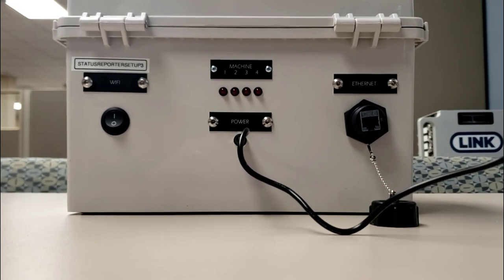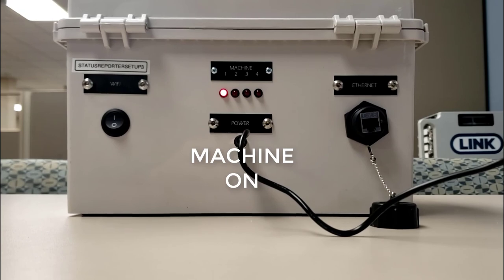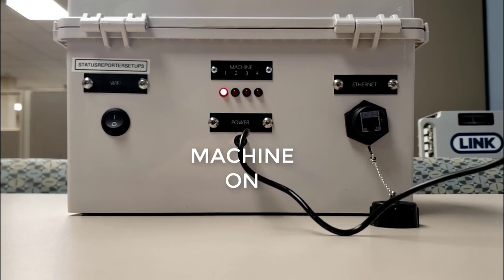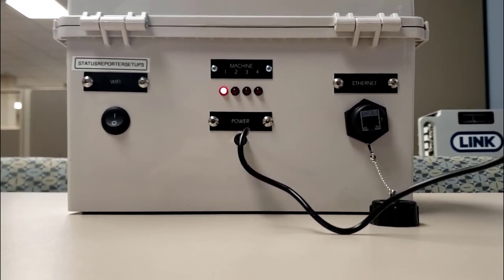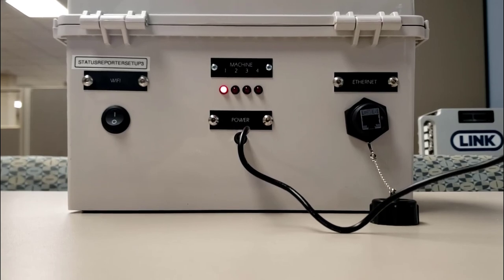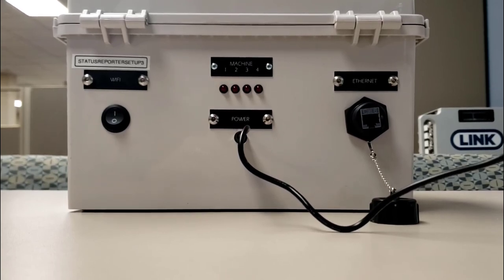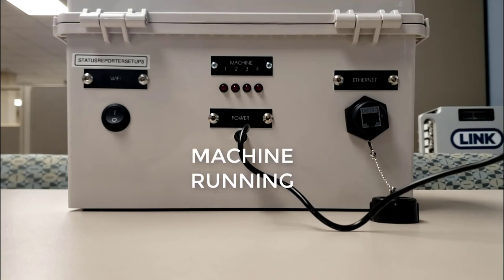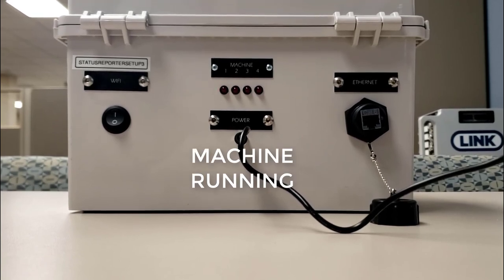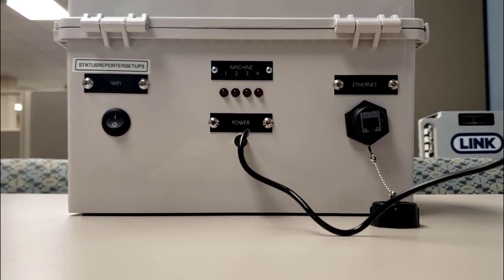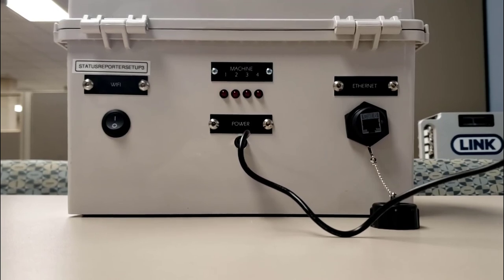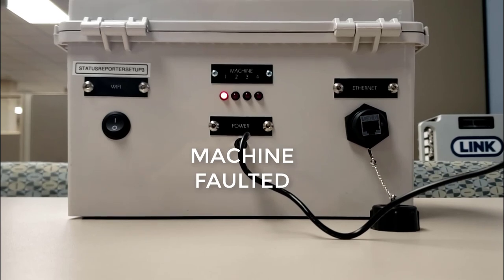Now to show how the LEDs work for each machine status, we'll turn machine 1 on, and you'll see a solid LED. Then we'll show machine running, and we will see the LED blink at a relatively slow rate. And then finally, we'll show machine faulted condition, which will be a much faster blinking rate with a pause.